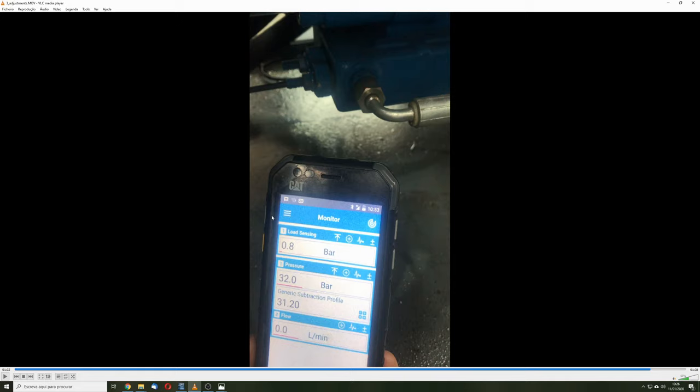And now an aside, you can ask me, well, why should I worry about having the load sensing so low in this particular case? I mean, come on, this is a drilling rig. It will run flat out most of the time anyways, and we already saw that when the pump is maxed out and the spool is shifted completely, the pressure drop is very low, so why should we care? And I say that, yeah, you are right, it will work, of course, but don't forget that there are two more functions that may require partial flow, and in any case, making the system a little bit more efficient is never a bad thing, but I do see your point.